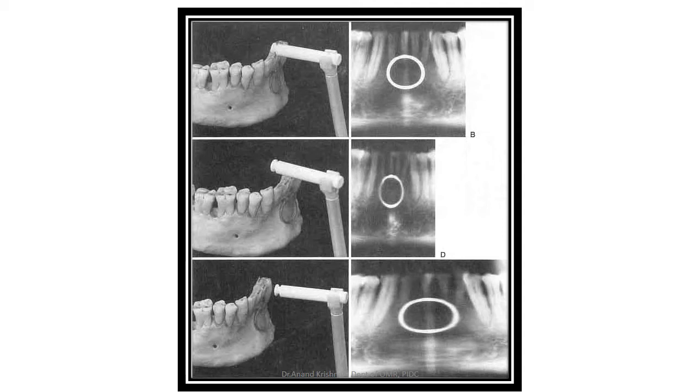Let us say the patient bites a little anterior and comes way in front of the focal trough. Just for reference, a concentric ring has been placed below the lower anteriors to show what kind of image distortion happens when the object is not brought within the focal trough. When he bites a little anterior, you can see that the ring narrows down.